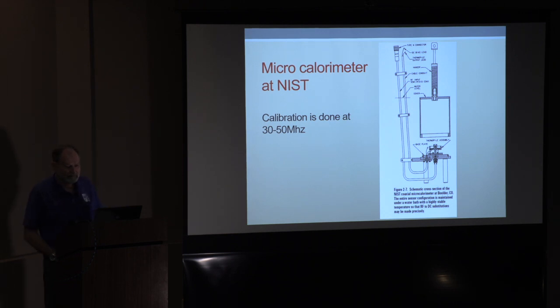Now, if you've been running a GPS frequency source in your shack, you're regularly dealing with 11 digits of accuracy. If you have a nice DC voltmeter, you've got 5.5 or 6.5 digits of accuracy. If we can get 0.5% at RF, you're almost to the gold standard. That's almost as good as you can do. So these guys are fighting pretty high numbers from our point of view, and you'll see why as we move along.